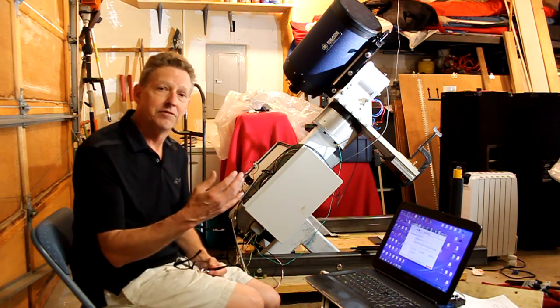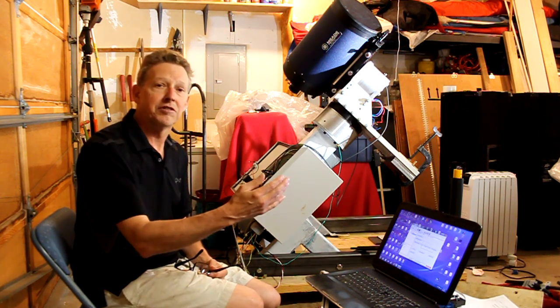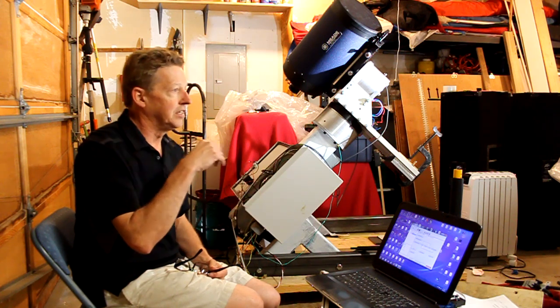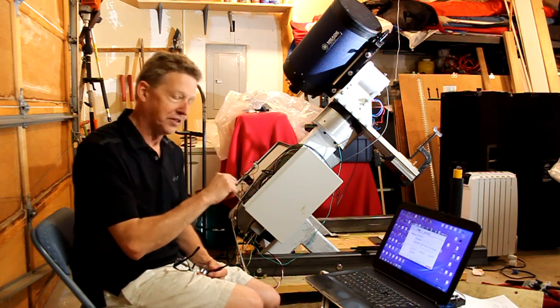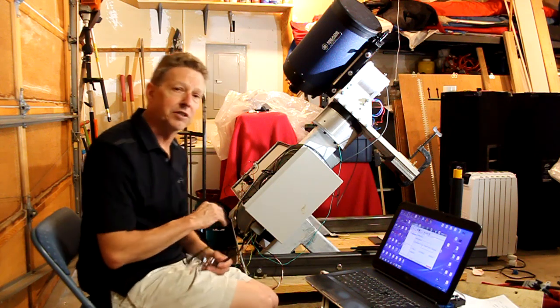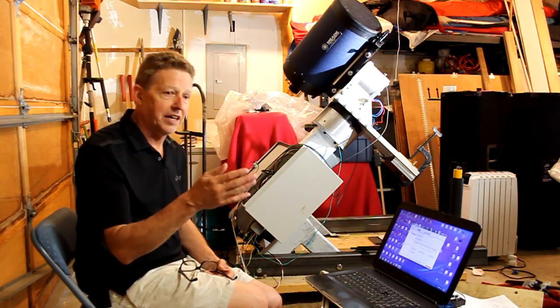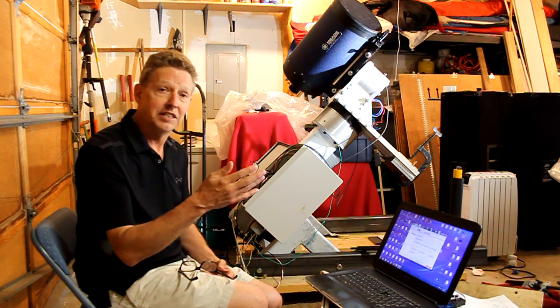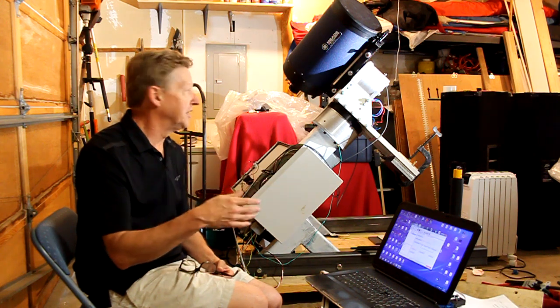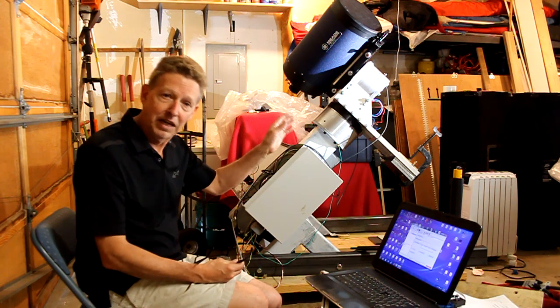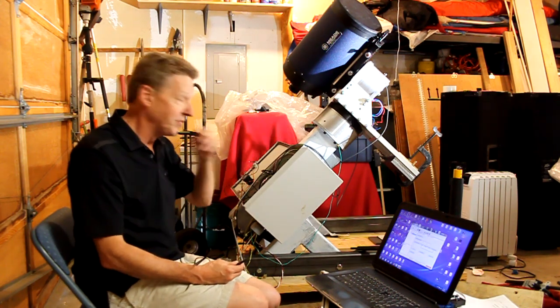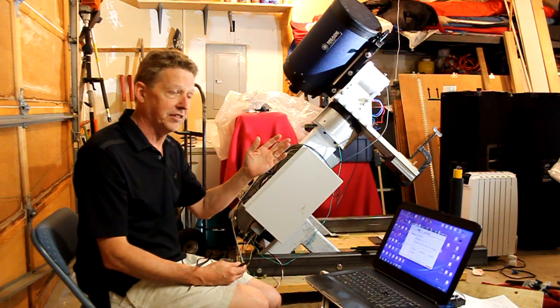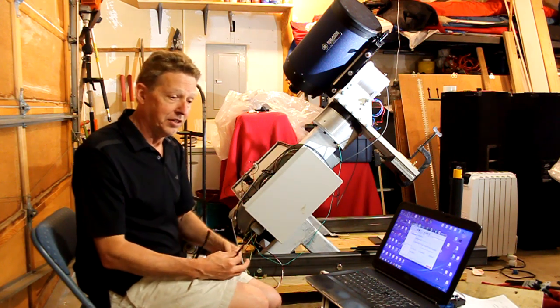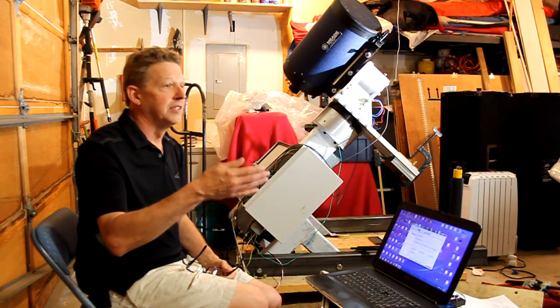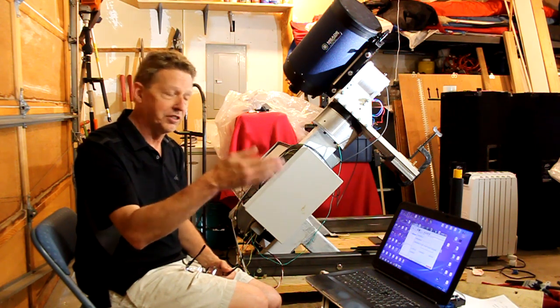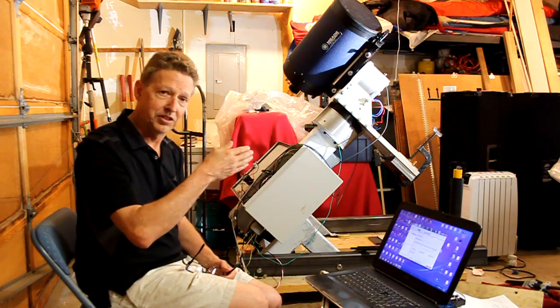In a servo drive, you have an inner loop, which is a current loop, the fastest loop. At the most fundamental level, what the drive does is drive current to the motor windings, so it's creating current. The next loop outside of that is a velocity loop. It controls the speed, and the speed is sensed by the encoder by taking the derivative of position. And outside of that is a position loop. Okay, so we tune from the inside out. We tune the current loop first, the velocity loop, and then the position loop.